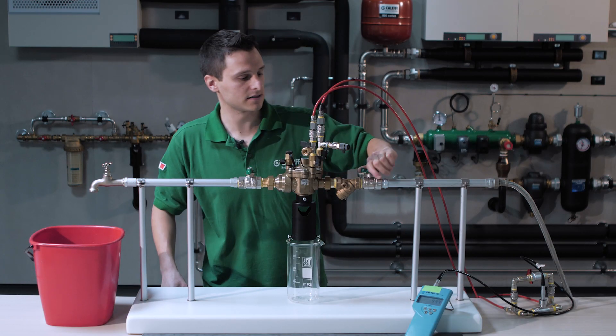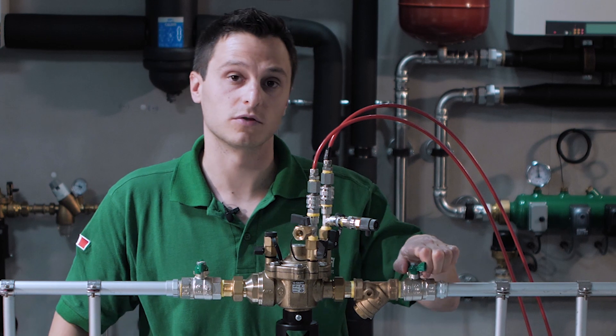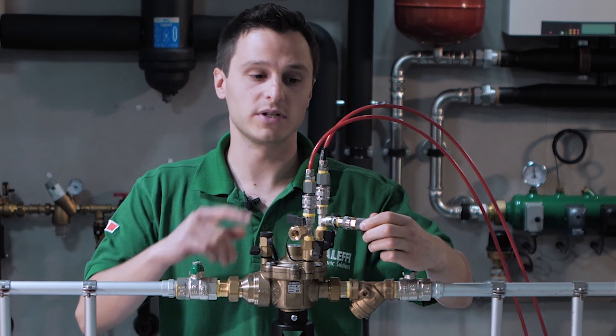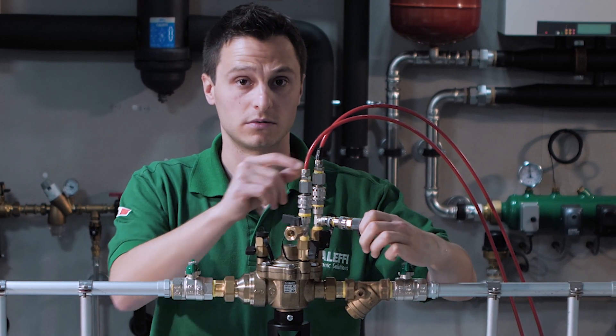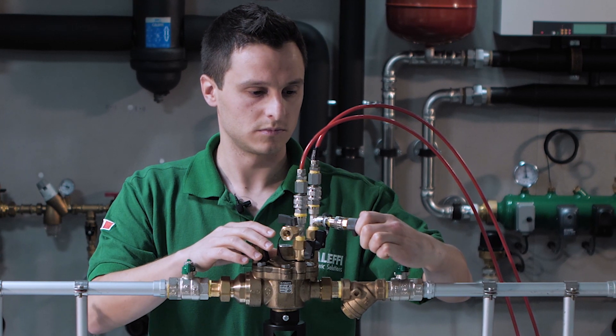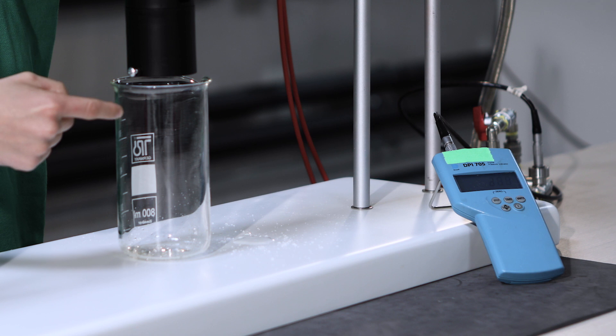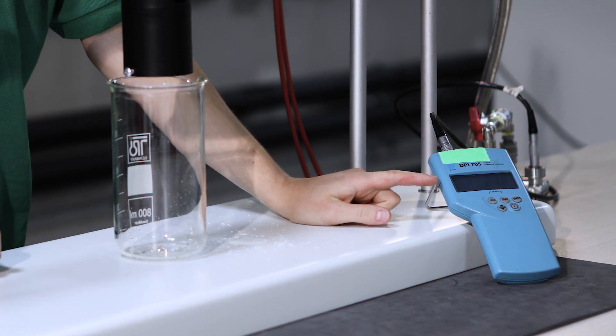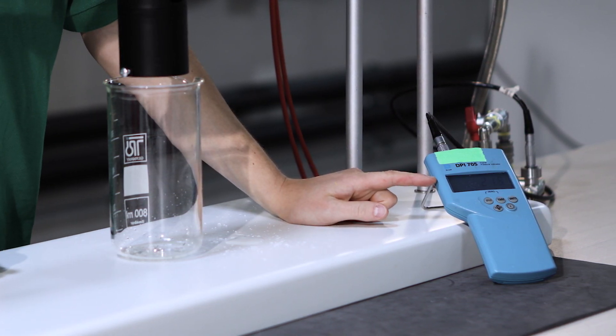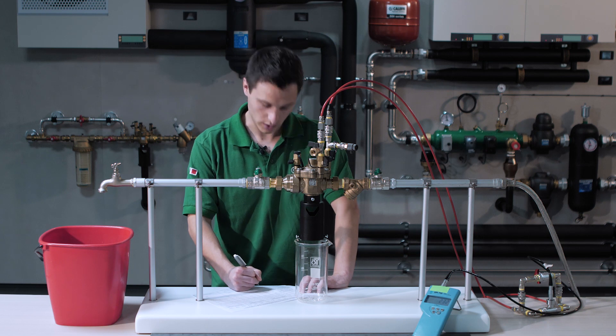For the second test, close the upstream shutoff valve and decrease the pressure in the upstream chamber. When the device starts dripping from the discharge line, read the value on the display and take note of it.